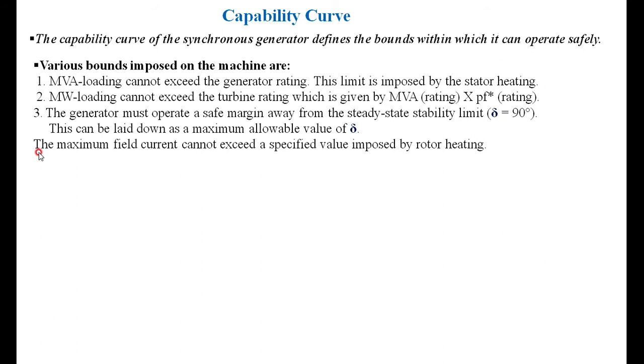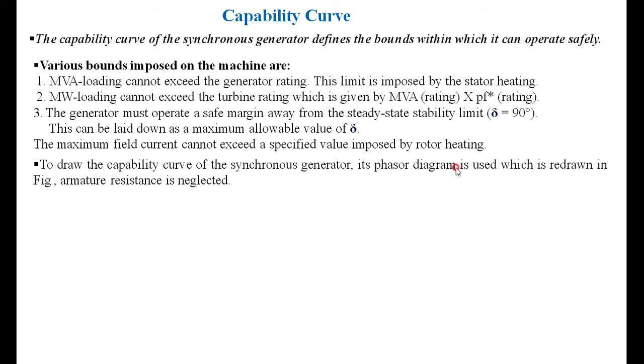The fourth limitation is that the maximum field current cannot exceed a specified value imposed by the rotor rating. That is, you should not exceed the field current beyond its rated value as specified on the machine. To draw the capability curve of a synchronous generator, first we have to construct the phasor diagram of the alternator, and then derive the capability curves from it.